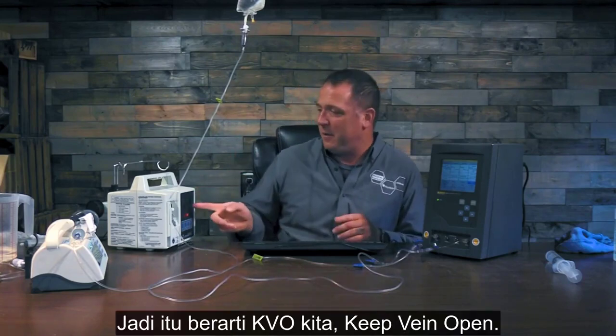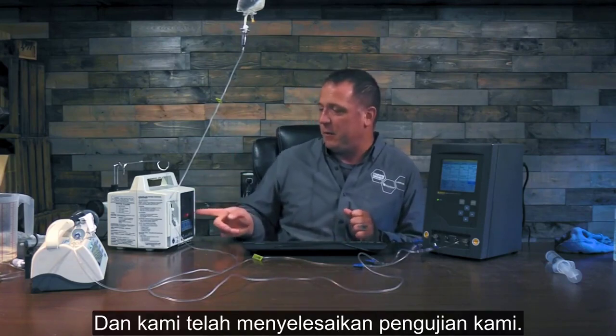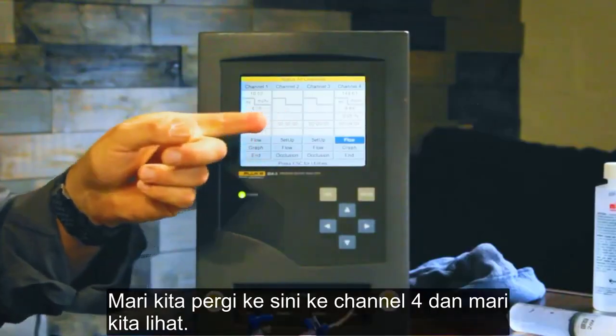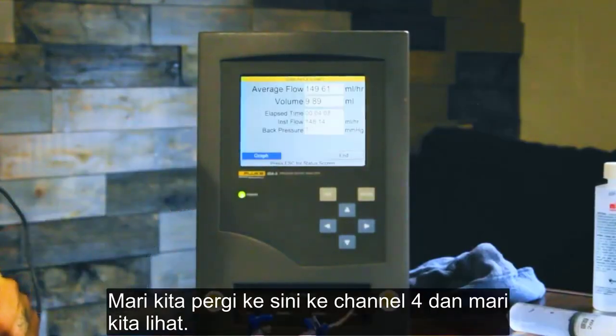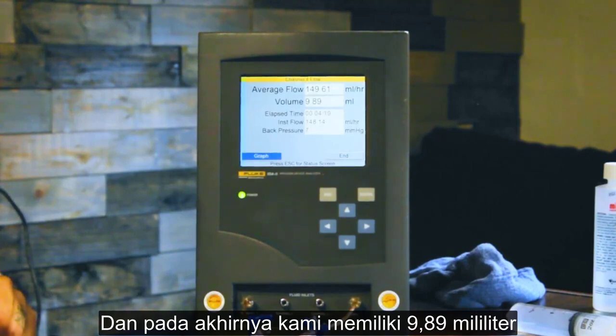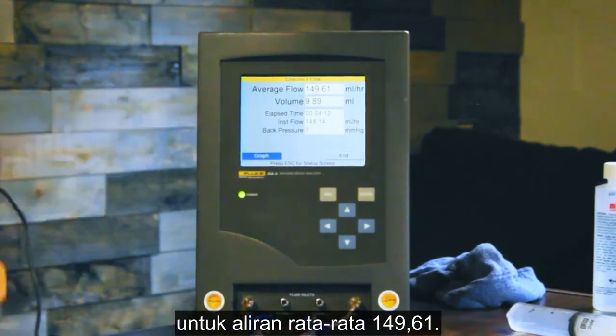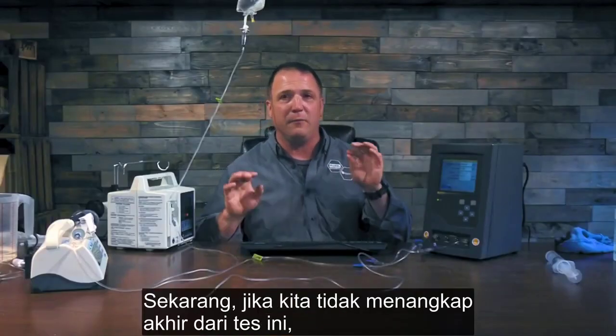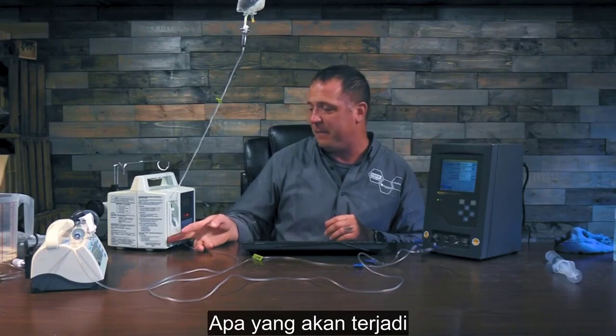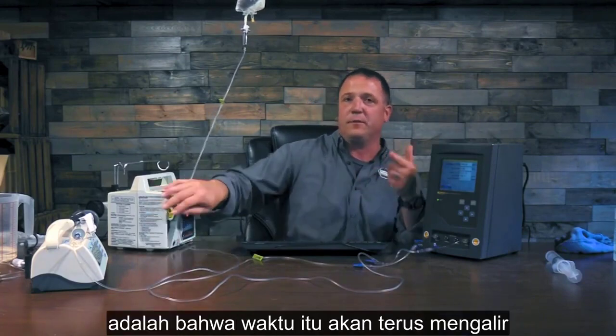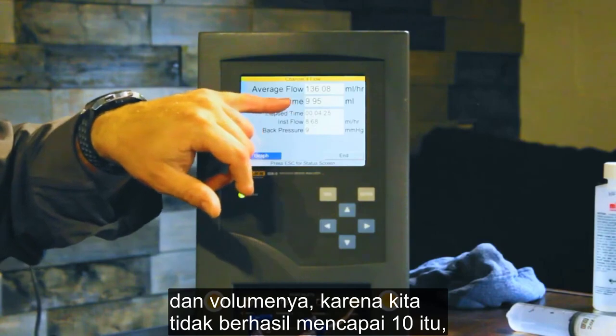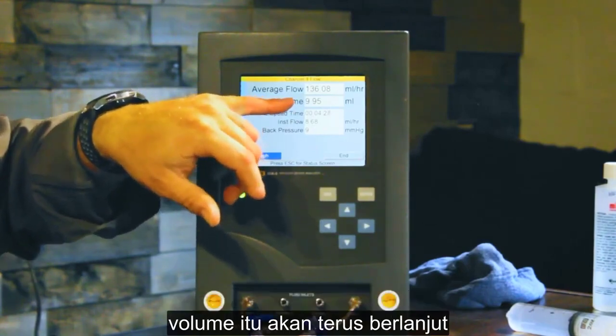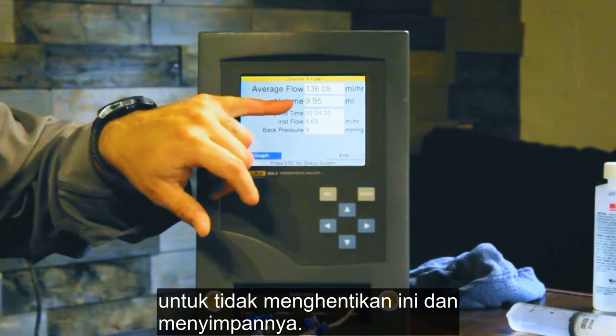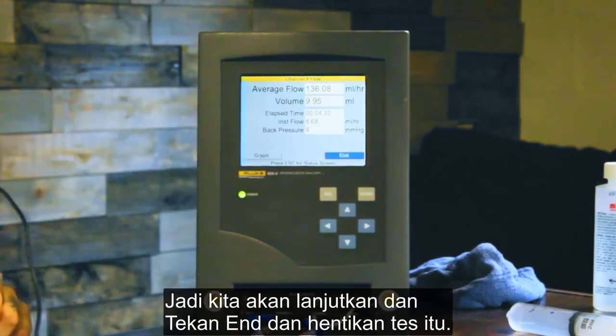There's an alarm. So that means our KVO is open, our keep vein open, and we've completed our test. So let's go here to channel 4, and let's view it. And at the end, we have 9.89 milliliters for an average flow of 149.61. That's perfect. Now, if we didn't catch the end of this test, that time is going to continue to flow. And the volume, since we didn't make it to that 10, is going to continue to not stop this and save it. So we're going to go ahead and hit end and stop that test.